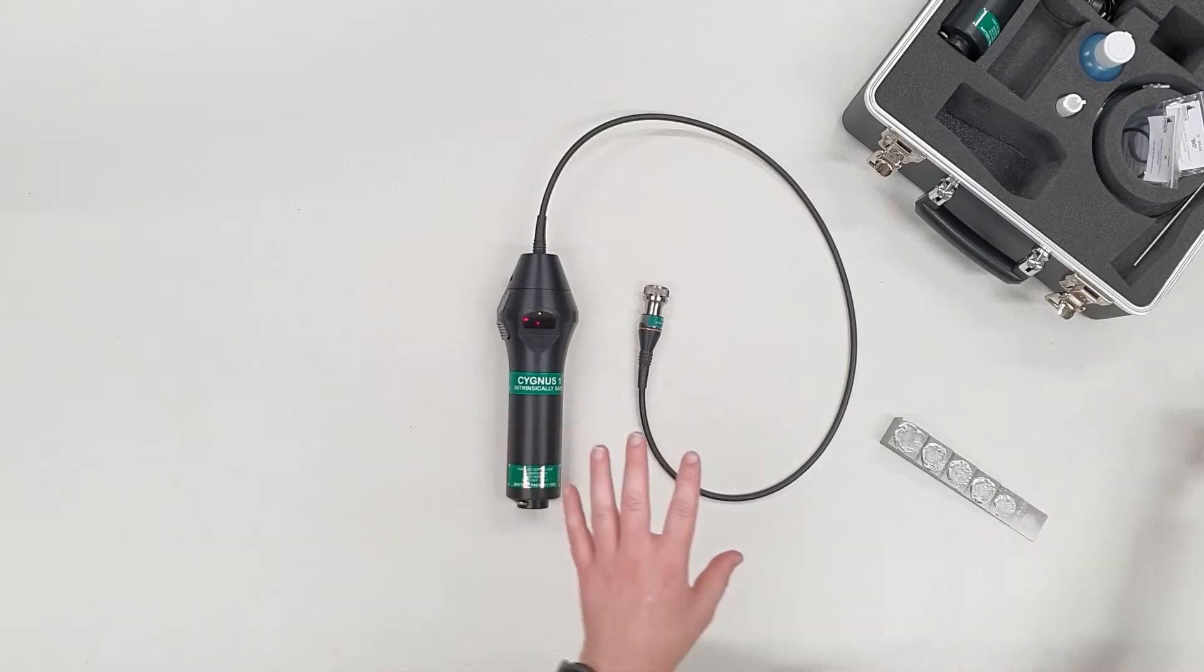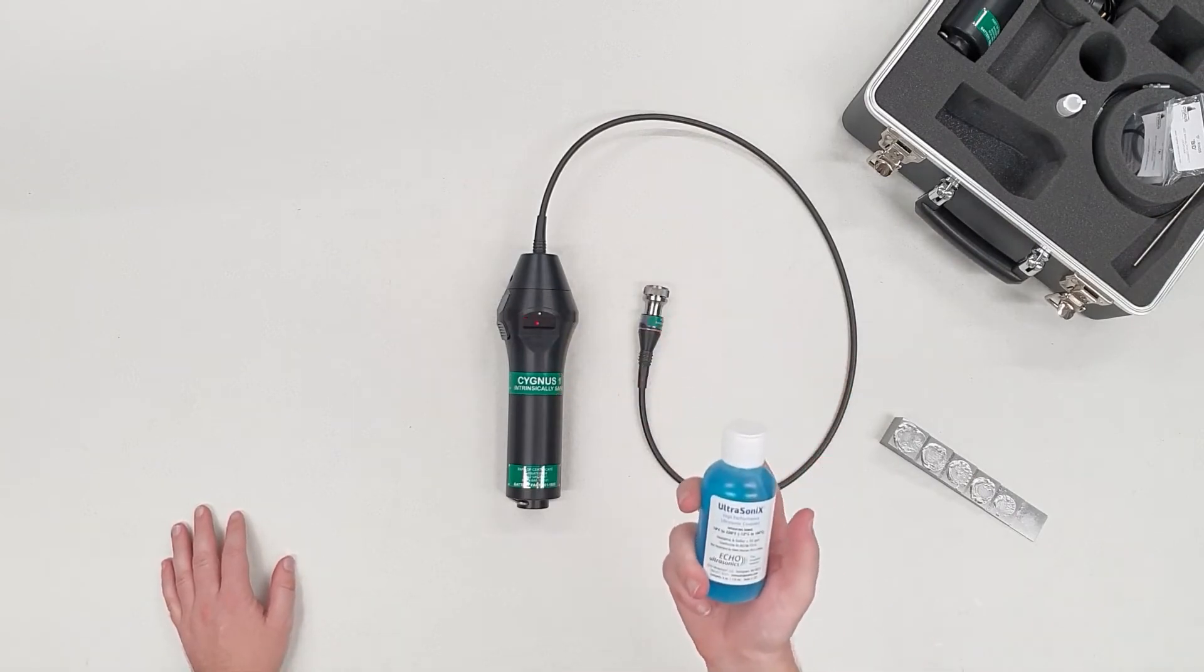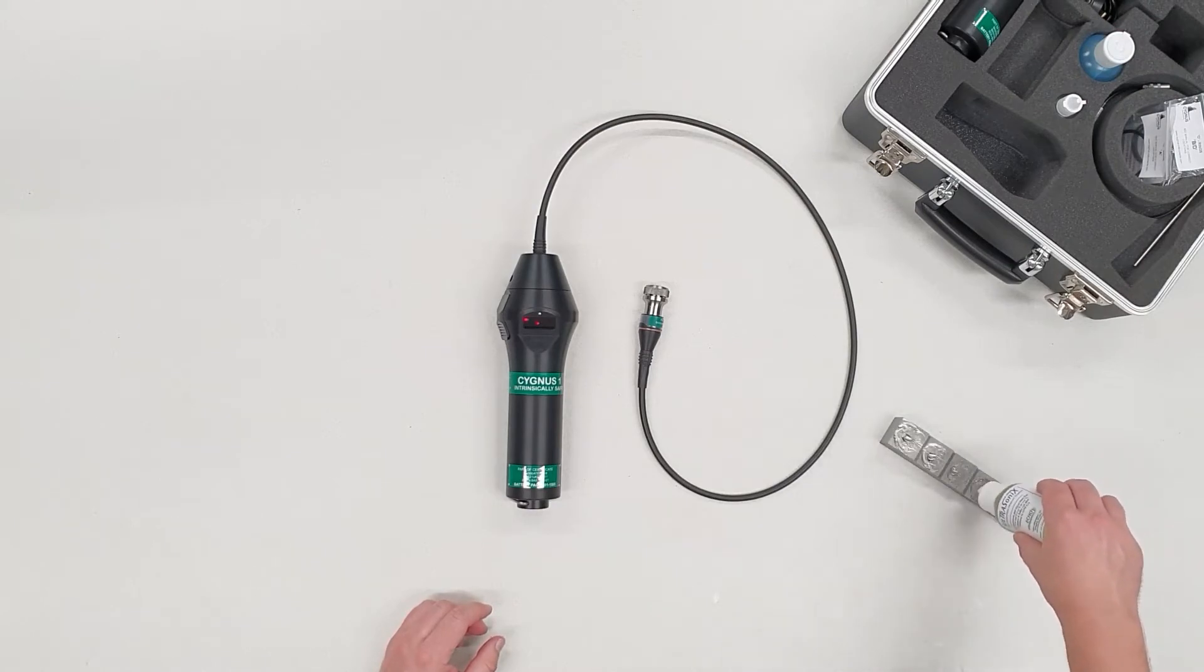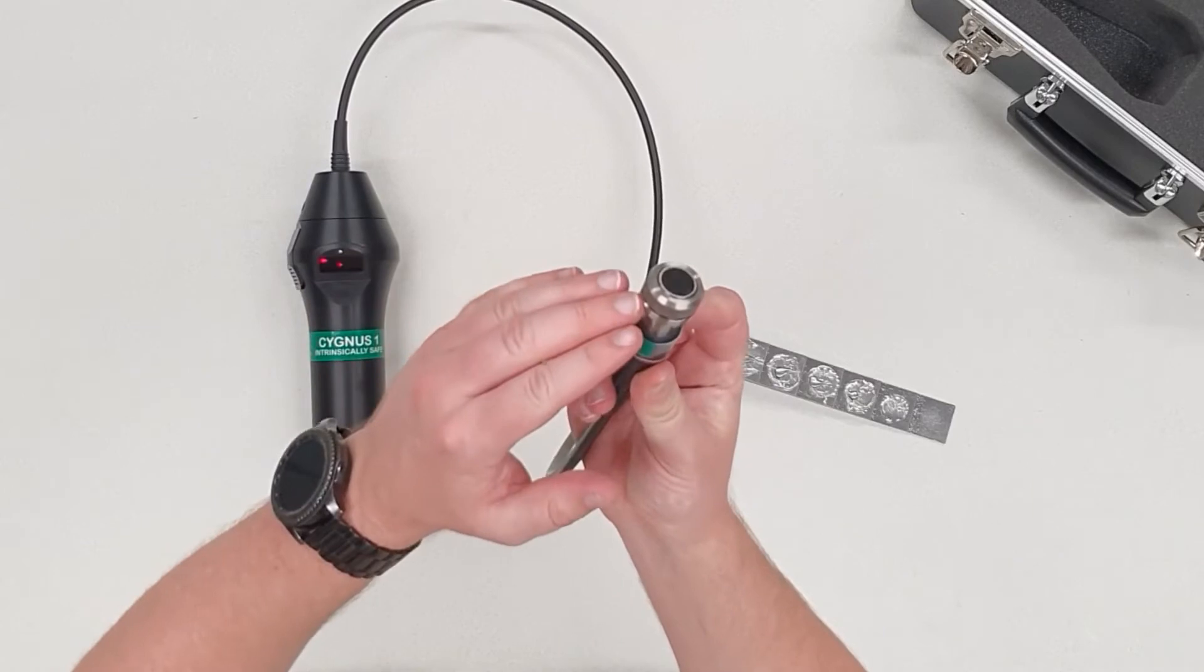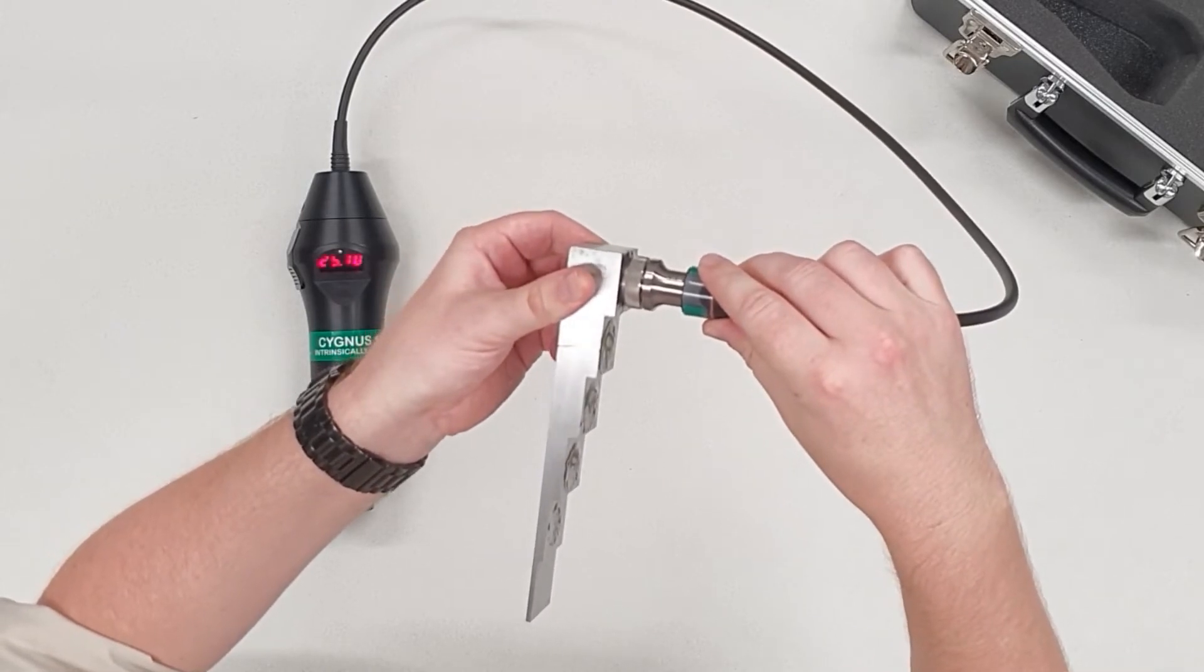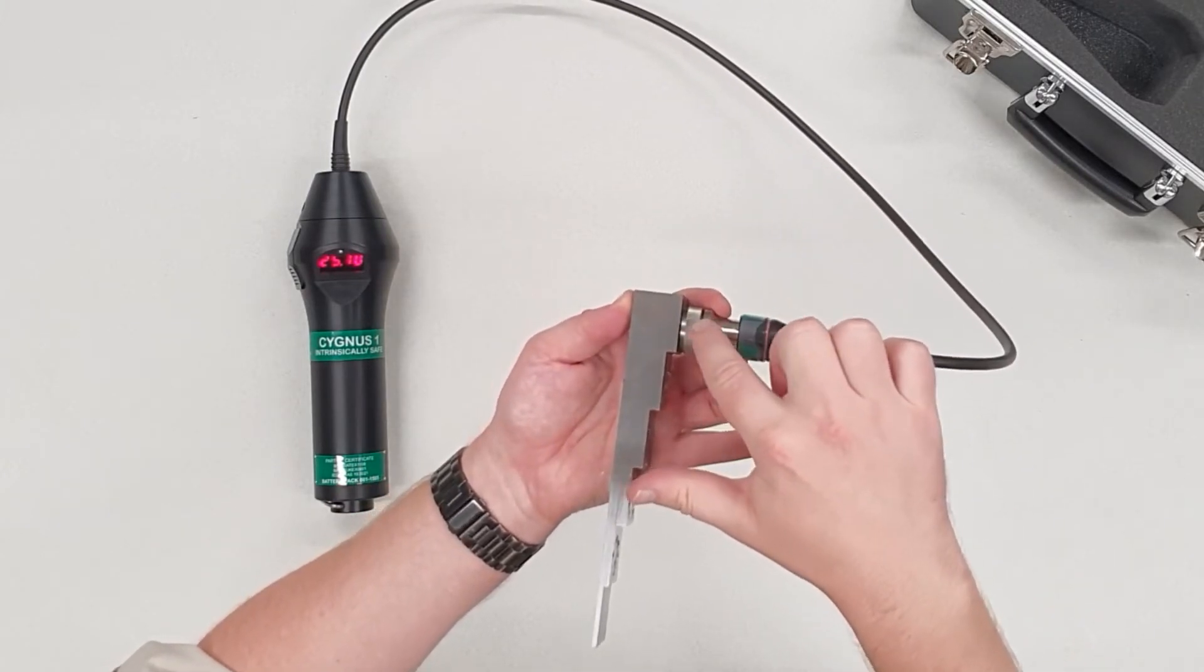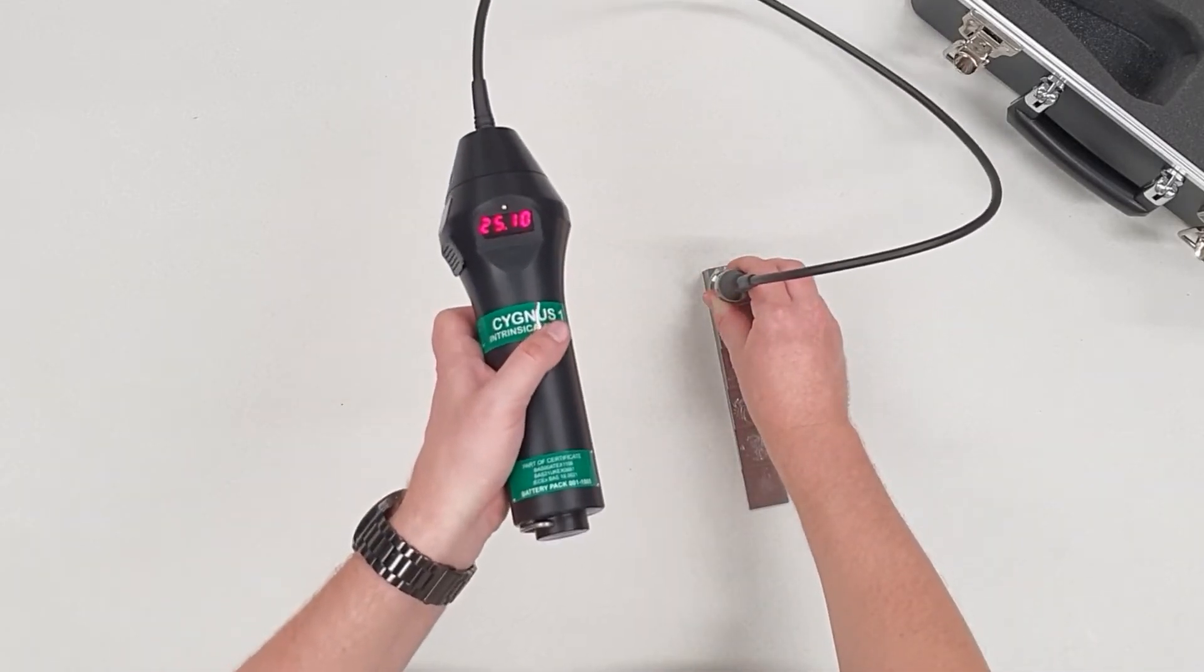It's very similar to yelling echo into a canyon and listening for the response. Unlike yelling, ultrasound does not travel through air very well. So you need to use what's known as couplant. You can also use oil or water if absolutely necessary, just anything that will remove the air between the probe and the part. Simply put a little bit of couplant on your block or sample. It doesn't need to be very much, just need to remove the air.